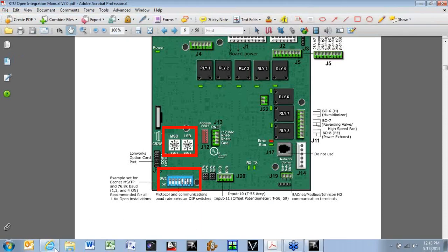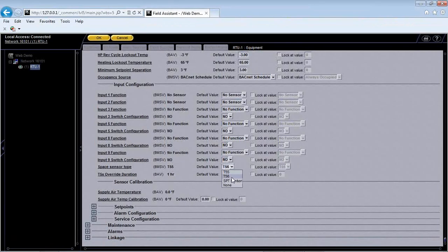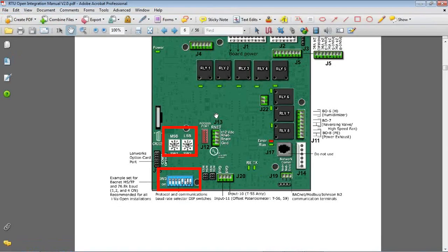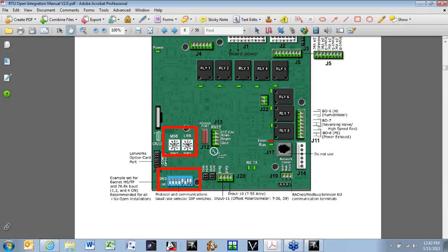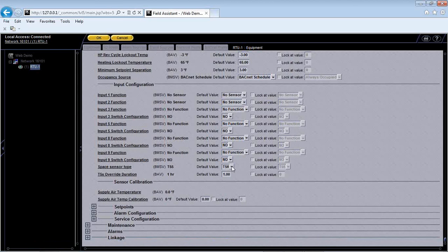The final sensor you can get is an SPT sensor, which is a Carrier communicating sensor, okay? Now this sensor is a 4-wire sensor. It wires into the plug called RNet on J13. Okay, it's a 4-wire sensor. You can use normal thermostat wire, 18 gauge is fine. But there's 4 different types of these SPT sensors. They all wire the same, but there are different options.